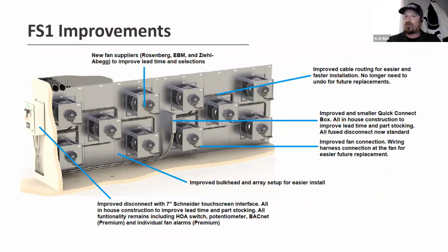We've improved the wiring, routing, and the wiring harnesses. Now the connections are made at the fans versus back to the quick connect box for each individual fan. It used to be that fan one had its wiring harness from the motor all the way back to the quick connect box. So if that fan were to fail, you'd have to order that particular fan and that wiring harness to come with it. This time now everything connects regardless, so fans are almost interchangeable where they need to be placed in the system.